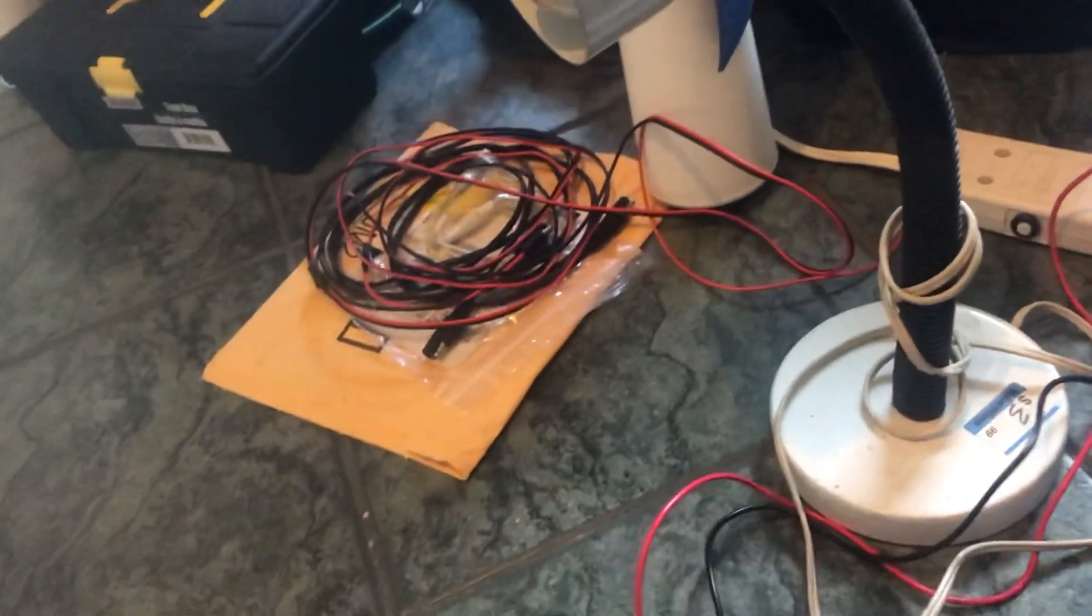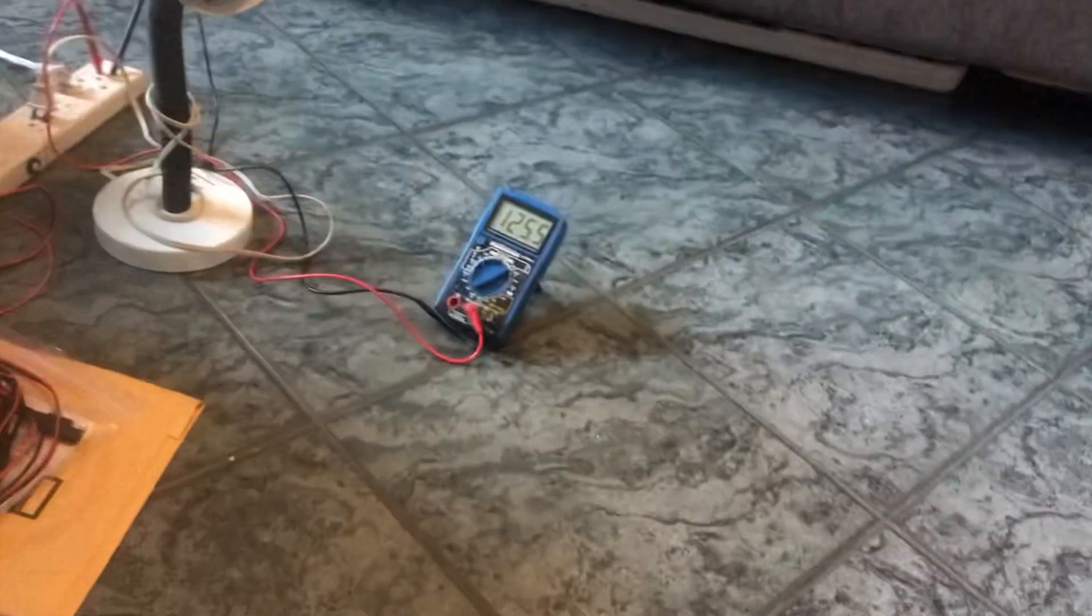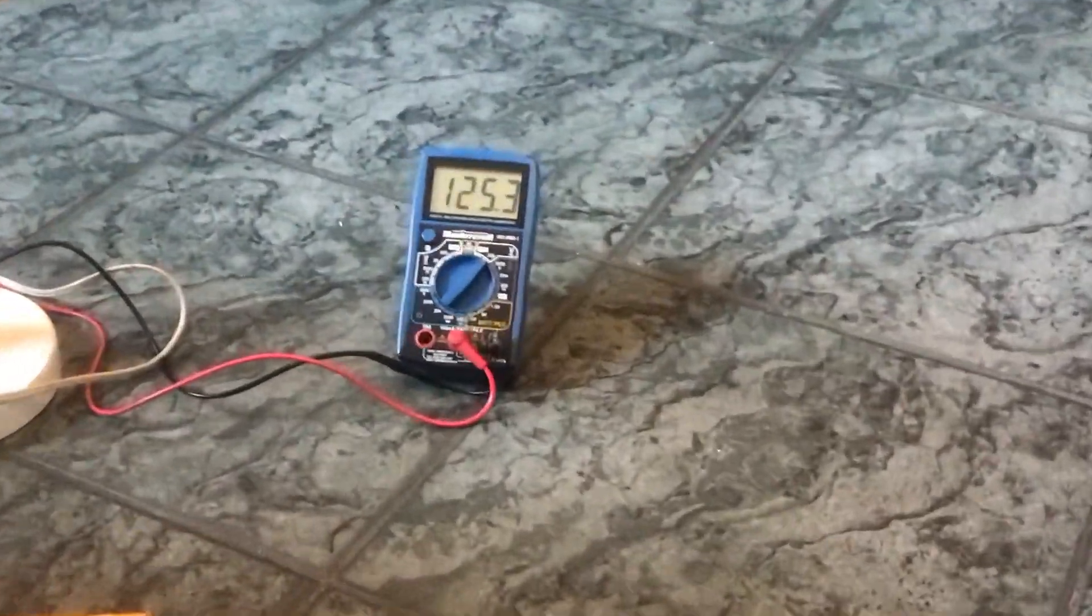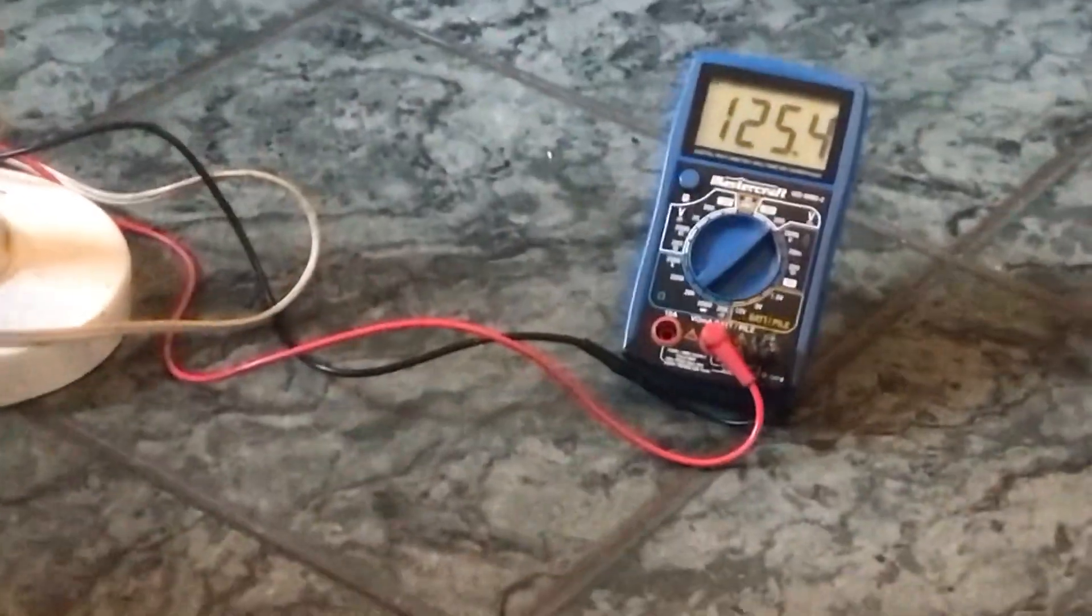I can even increase the voltage of the generator simply by adjusting the frequency. Now watch, 125 volts. Let's tune in. I'm going to increase it to 70 hertz.